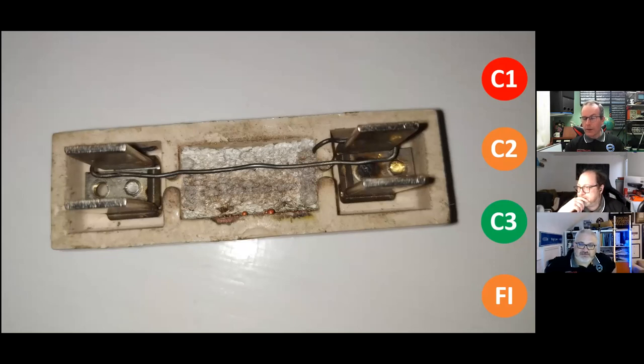Well, it looks like there's some scorching there. Yeah. Little ball of molten copper on the bottom edge there. Our favourite one, the old asbestos pad. So, okay. It's definitely C2 without a doubt as a minimum. And to be perfectly frank, I would say definitely C2 as a minimum in a house. I would probably put a danger notification in a home with obviously asbestos present, I mean... You're going to have that though. I mean, I've got asbestos on my shed.